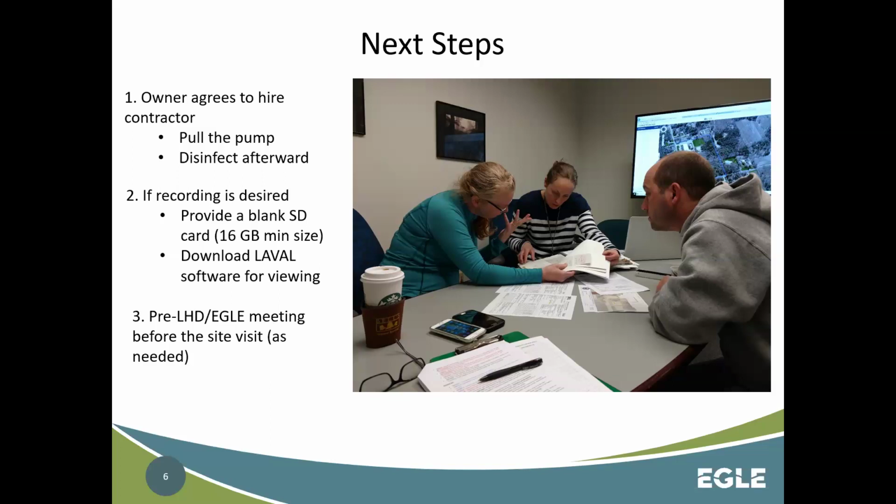Basically, the way it works is the owner agrees to hire the contractor, which they would have to do at their own expense. The contractor would pull the pump and disinfect afterwards. We ask that they actually pull the pump at least 24 hours before we come out. There's been some instances where I've gone out to wells where there's quite a bit of sediment and material and debris in the well, and it just looks like pea soup, and we're just not able to see anything. So we want to give the well some time to settle out before we get there.